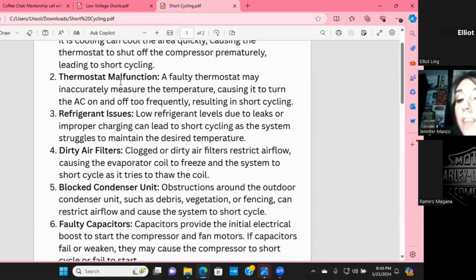And that means that when the unit is running, it's feeding power to the thermostat. When the unit is not running, it is not feeding power to the thermostat. So what happens is the Nest then dies and you have to pull it off the wall and charge it. And for that whole time, your system is off. That is probably the biggest one that I see where a thermostat malfunction caused short cycling. It was either flickering because the battery is getting ready to die, or because the wire wasn't fully on RC, or because it didn't have a common at all.